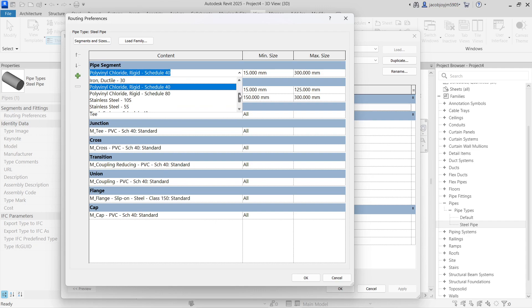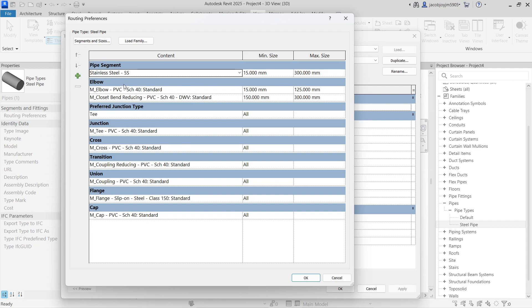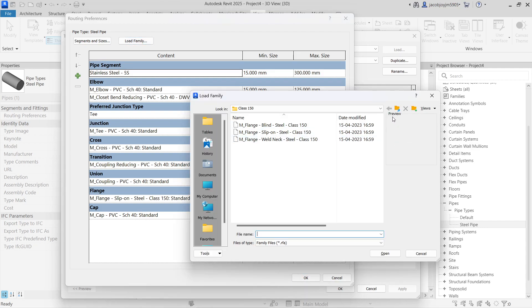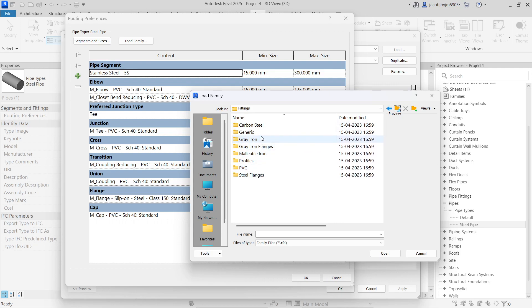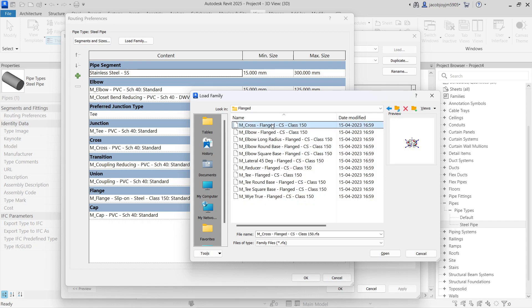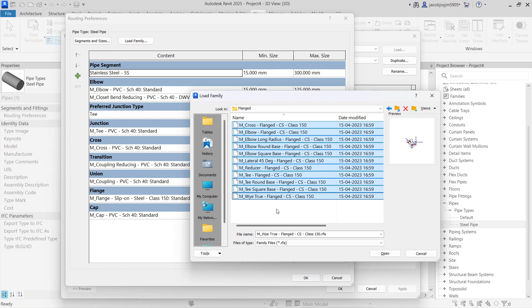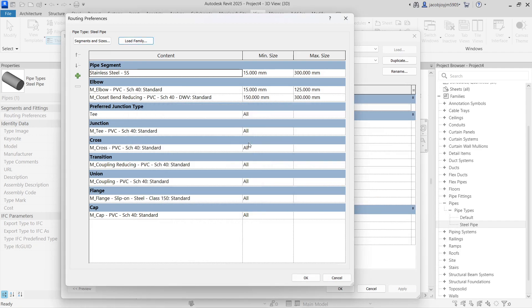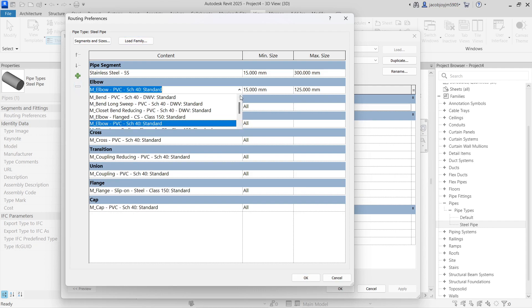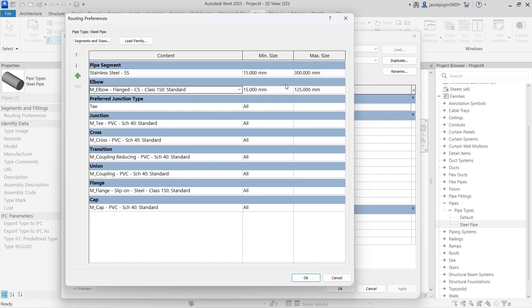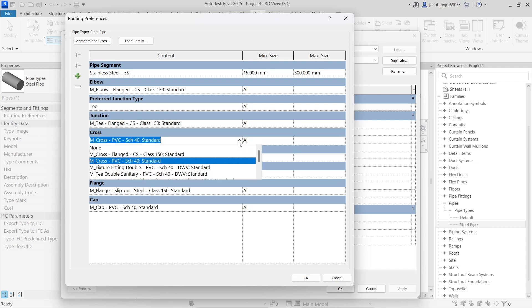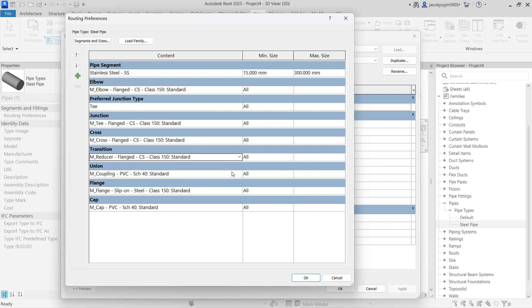We need to change the pipe segment to Iron or Stainless Steel for the steel pipe, and the fittings should also be steel. Load the family from the Carbon Steel folder in the Steel folder. Load all the fittings. If you don't need two rows you can remove one. Select Carbon Steel Class 150, all sizes.